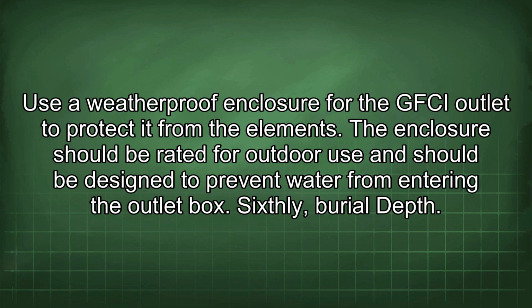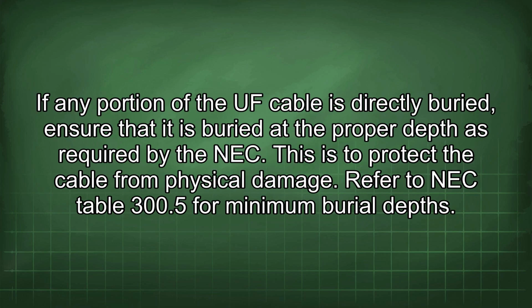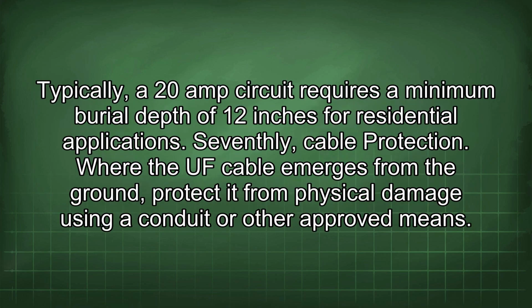Sixthly, burial depth. If any portion of the UF cable is directly buried, ensure that it is buried at the proper depth as required by the NEC. This is to protect the cable from physical damage. Refer to NEC Table 300.5 for minimum burial depths. Typically, a 20-amp circuit requires a minimum burial depth of 12 inches for residential applications.